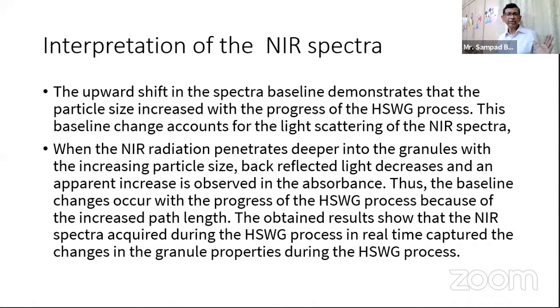And this captured the changes in the granulation property in real time. It is interpreted as a particle size increase. That is when particle coalescing takes place, the different stages of granulation pass, particle size increases, water bridges form, and then agglomeration takes place. The water is getting distributed. By measuring the water reflectance, the time lag and the change in intensity at the water band, you can monitor and interpret that the particle size is changing and agglomeration is going on. And this is to be interpreted through chemometric software.